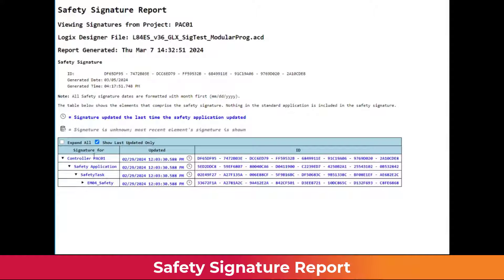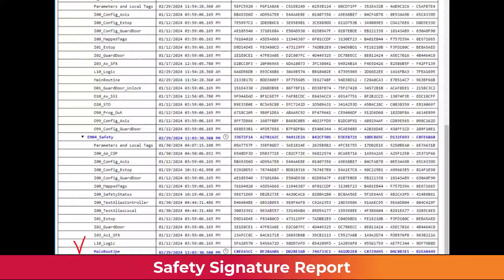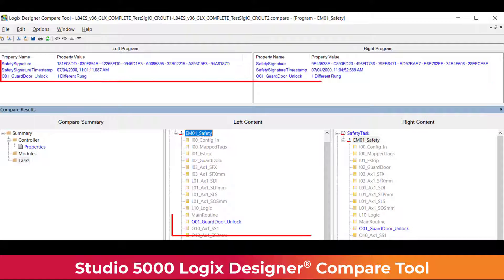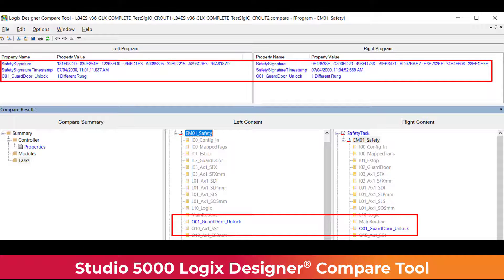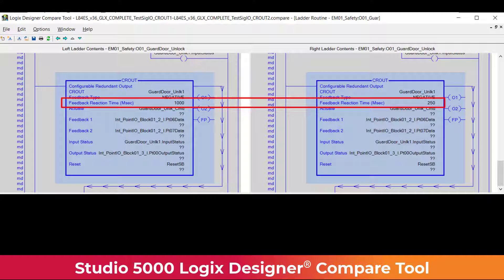The Safety Signature report can be used to determine where changes have been made in a safety application and, equally important, the safety elements that have not changed. The Logix Designer compare tool is useful for locating specific changes by comparing the current Logix Designer application project file to an archived project.